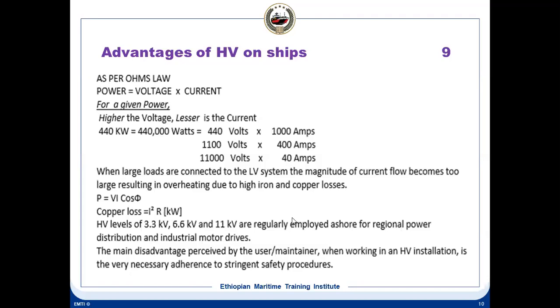So P is equal to VI cos phi, and copper loss is equal to I square R. See here also, you can see I square R. So the copper loss will go high as the current is going high. High voltage levels of 3.3 kV, 6.6 kV, 11 kV are regularly employed ashore. Normally you will find on our ships 3.3 to 6.6 kV. The main disadvantage for the user or a maintainer is that when you are working with high voltage, you need to have a lot of safety procedures. Your insulation requirements will increase. Because the voltage is increasing, the current is reducing.